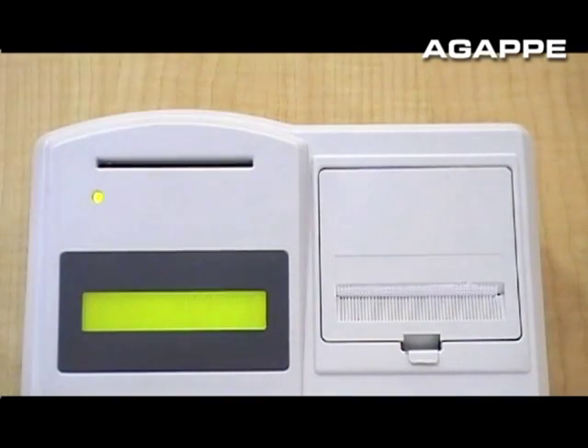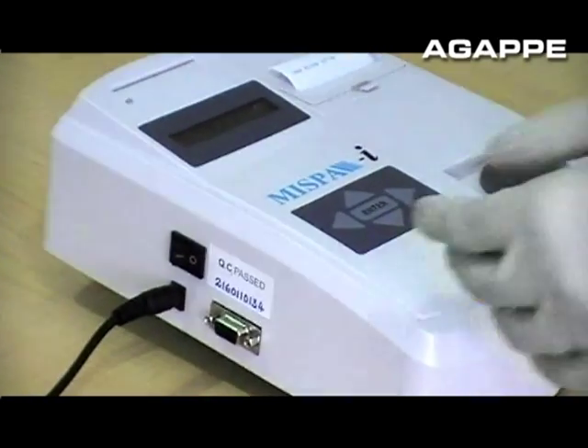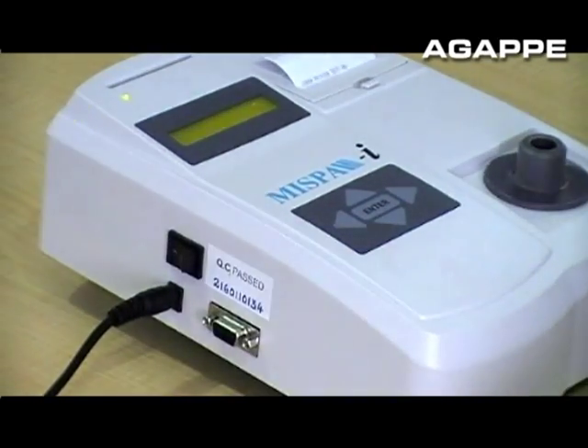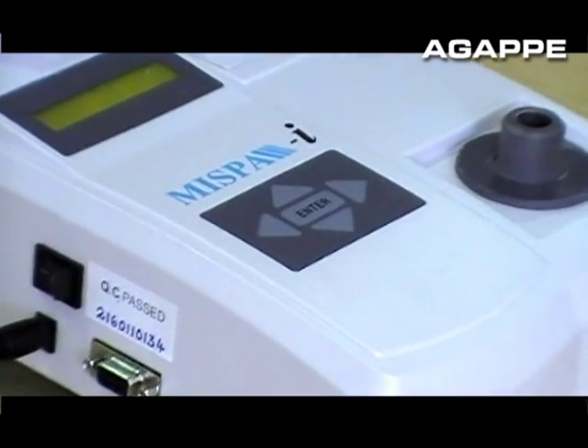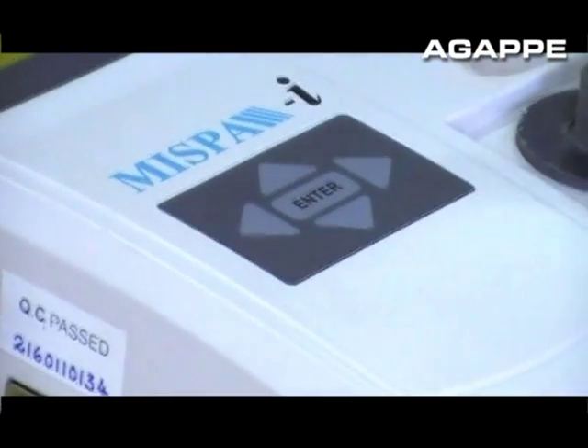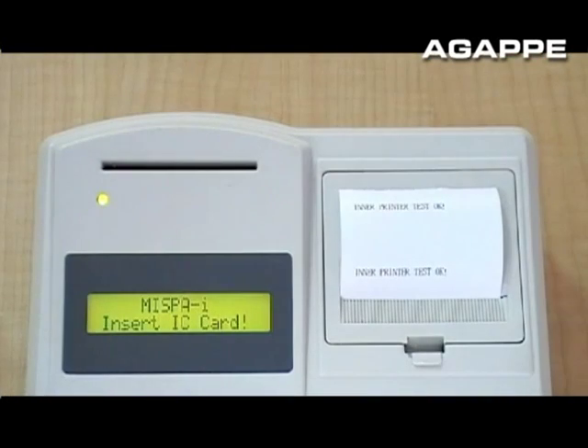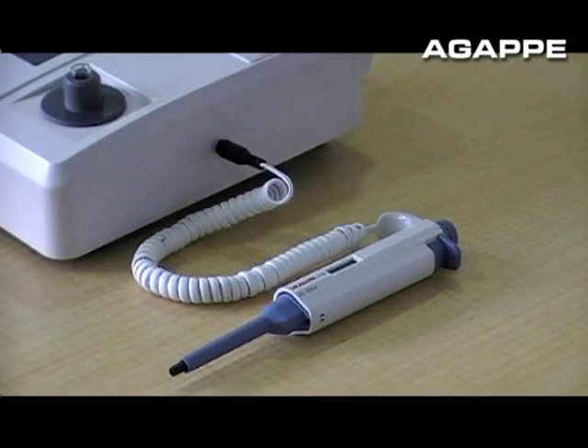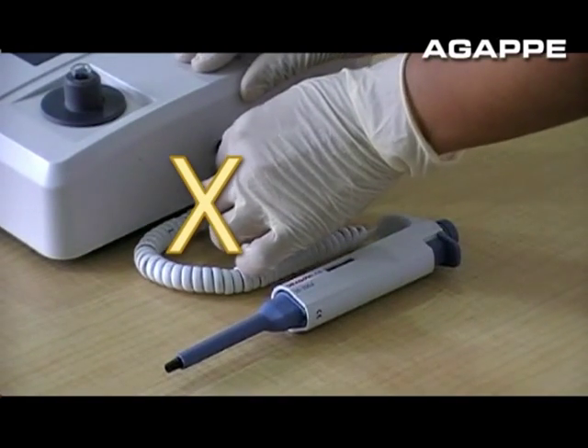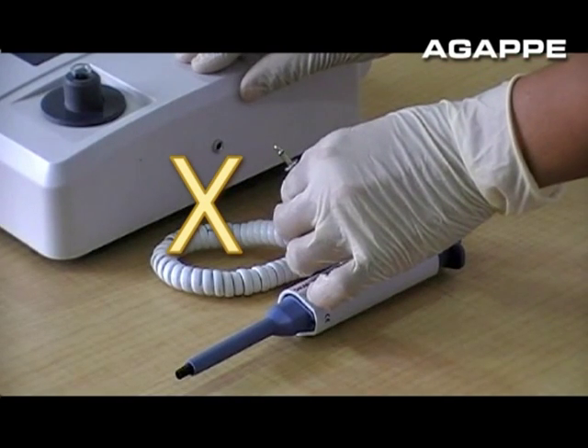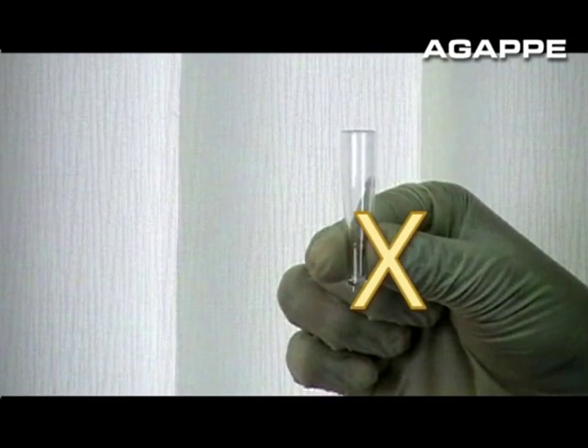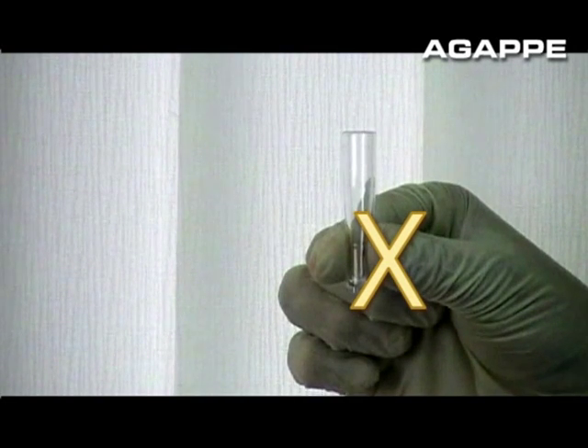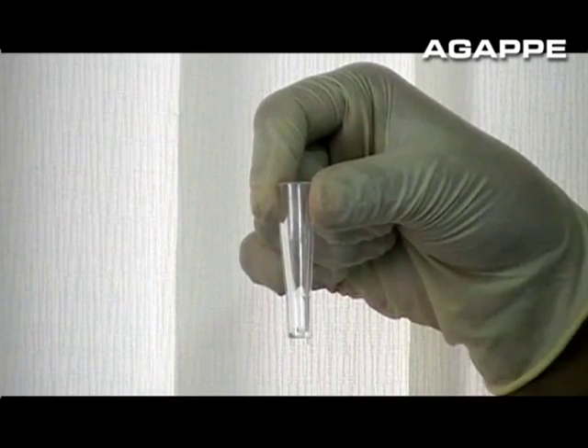Then restart the machine. Warm up is required after every power on. You can skip the warm up if you restart the equipment within half an hour by simply pressing the Enter key during the warm up period. That is, once the equipment has warmed up, you don't have to wait for the warm up to complete for a power down duration of 30 minutes. The electronic pipette attached to the machine is only meant for dispensing reagent R2. Don't use it for R1 or sample. Hold the cuvette properly. Don't touch the light path area, it may affect the accuracy of the result. Hold it at the top.